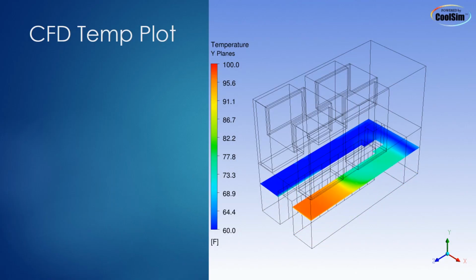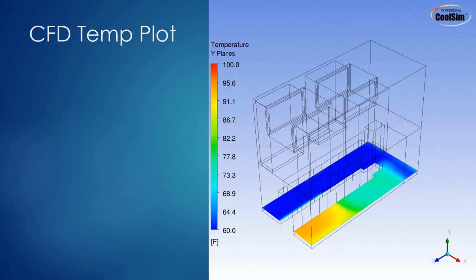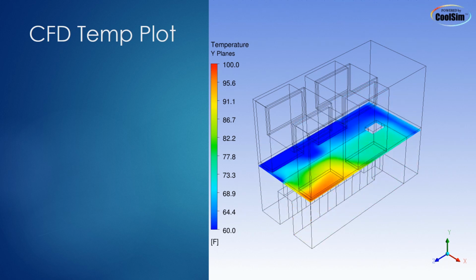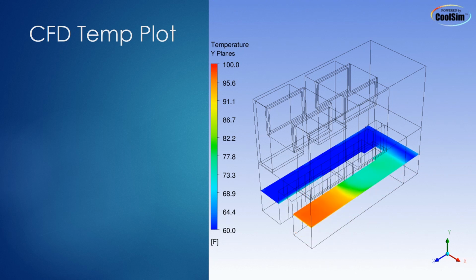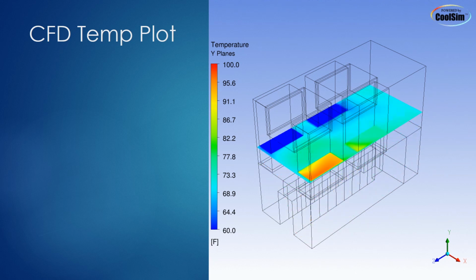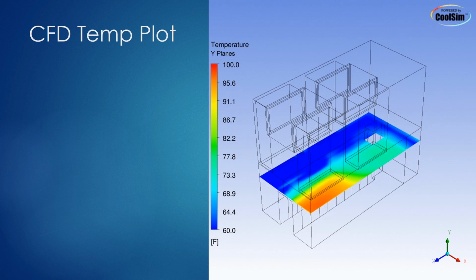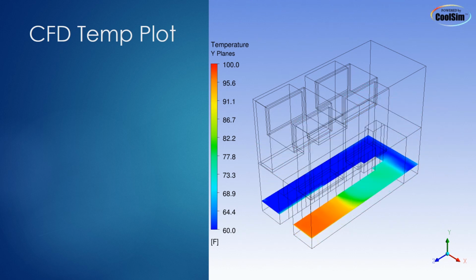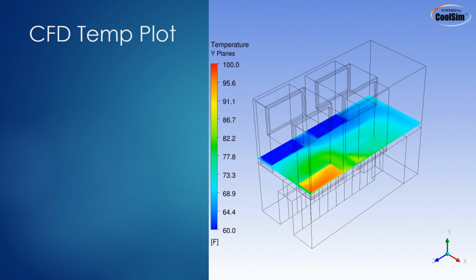So here's our CFD temperature plot of the HPC Vault that we're talking about. And you can see that the temperature in the cold aisle is around 60 degrees. It's pretty cold. But then the temperature delta into the hot aisle, because those servers are so hot, it gets almost up to 100 degrees. So this is a very specialized application where you're going from 60 degrees to about 100 degrees. And the great thing about that is that these rooftop air handler units really want to have high heat coming back. They run more efficiently in that kind of a configuration. So it makes it much more efficient to run this way than in a traditional colocation architecture.